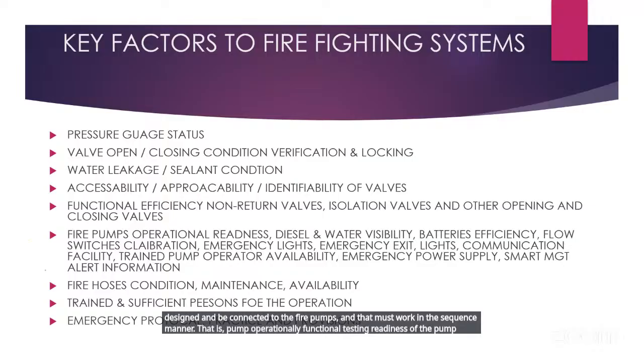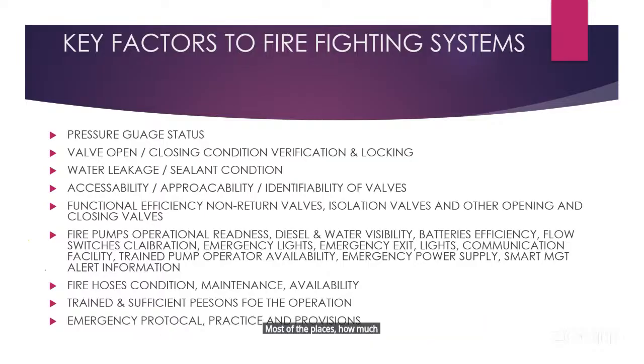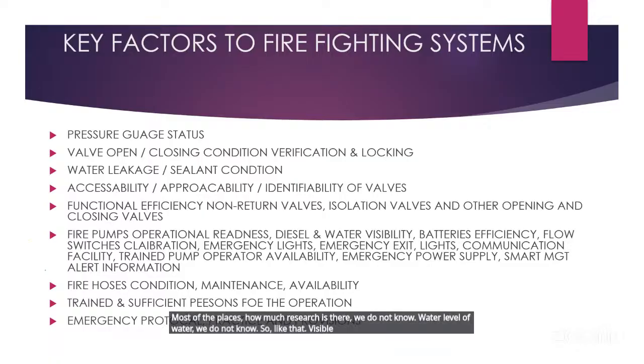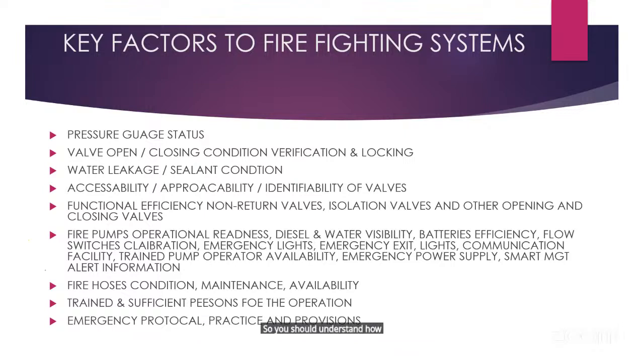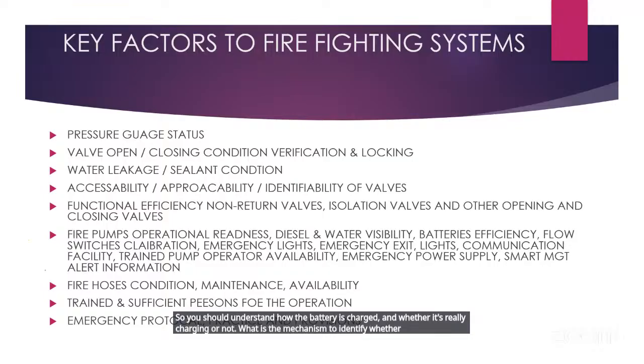Then the diesel and water visibility. In most places, we do not know how much diesel is there or the level of water. So a visible level indicator for water and diesel should be there. And battery efficiency is not tested. They say it is automatically recharging, but how do you know? They cannot answer. You should understand how the battery is charged and whether it is really charging, what the mechanism is to identify that, and whether it will overcharge. There must be a mechanism, and you must understand how it works.